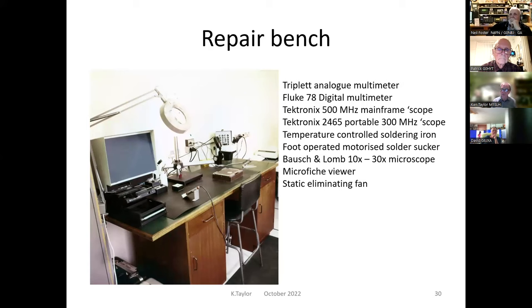Occasionally, when replacing a module, a slightly displaced pin would damage the connector at the back of the column. This would require some extremely delicate surgery, involving replacing the wire and reforming the connector with epoxy resin. Even rarer were production faults when a connector in the back plane had not been soldered, leading to an intermittent fault which could take months to find.